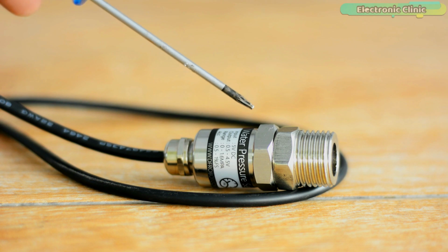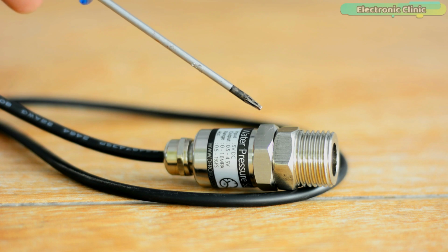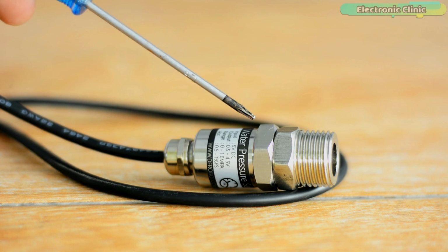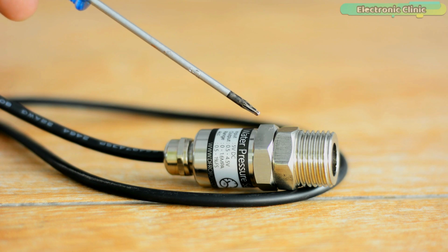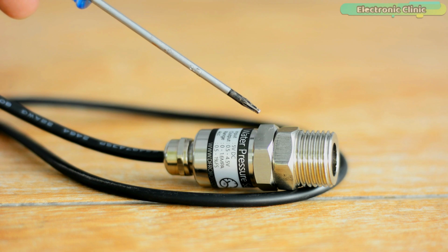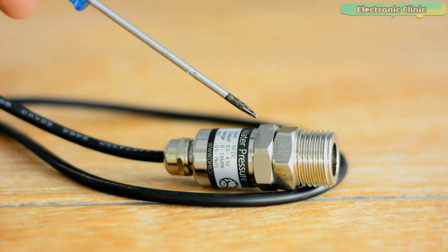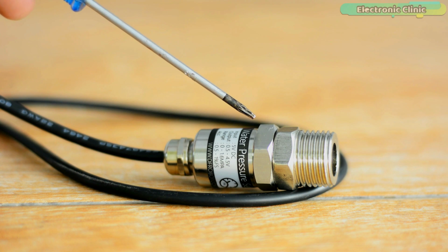Pressure greater than or equal to 3 megapascal will damage the sensor. The measurement accuracy is 0.5% at around 55 degrees Celsius. The waterproofing level is IP68. The operating temperature is from minus 20 to 85 degrees Celsius. The sensor response time is less than 2 milliseconds.